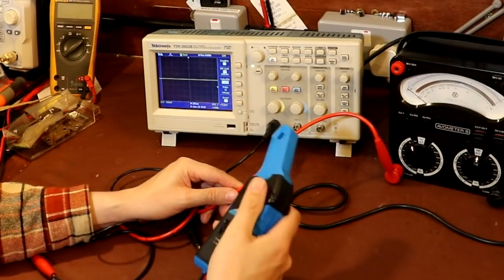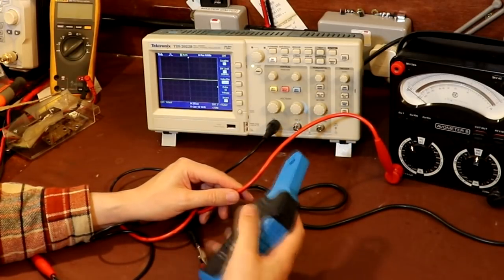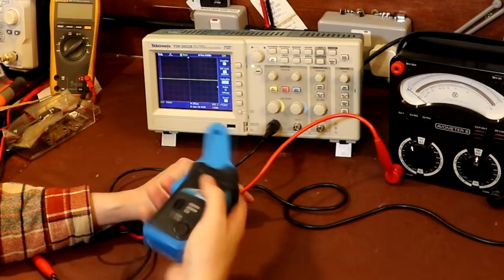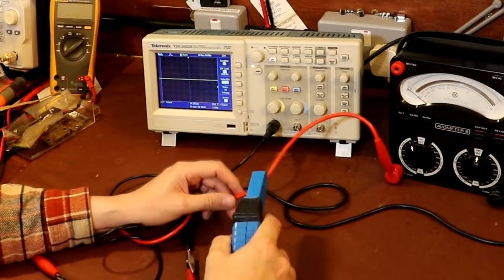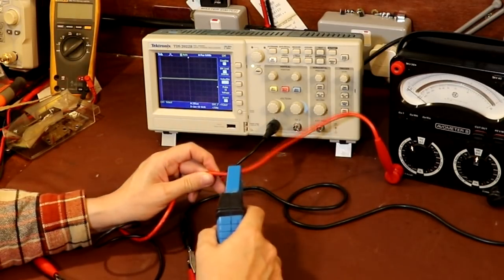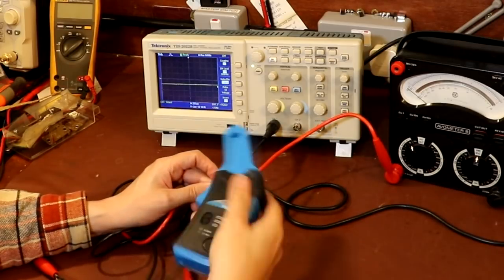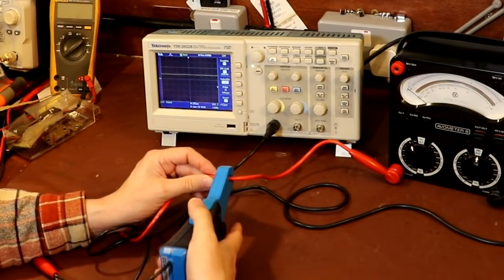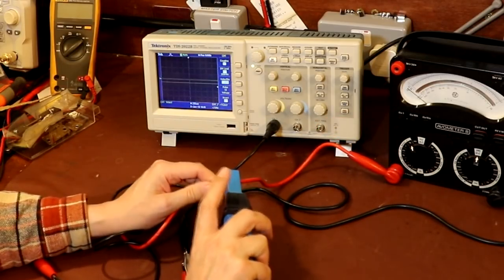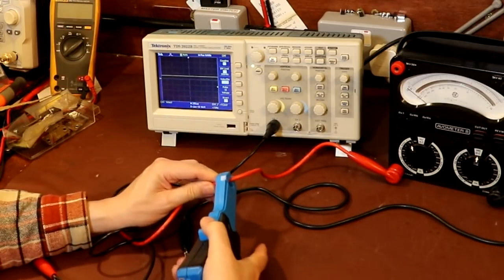Now, the other thing to note with your current clamp is if you actually put it on the other way around on your wire, you'll get a different reading. Let me show you that. So that's on that way, but if I turn the clamp round on the wire, it goes up. Not really a problem, just something you've got to know when using current clamps.